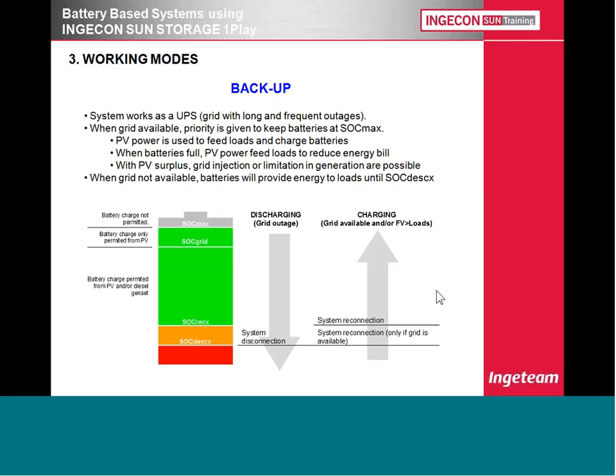In this system, as you can see, it's very similar to the previous case. We have the grid, we have optional PV in case you want. Some people don't want the PV power; they just want the batteries, and they want to use the system as a UPS. The system is very similar. You have the bypass contactor. But in this case, we need one extra element, which is this neutral to ground contactor, which is controlled by the inverter. Why do we need this neutral to ground contactor?